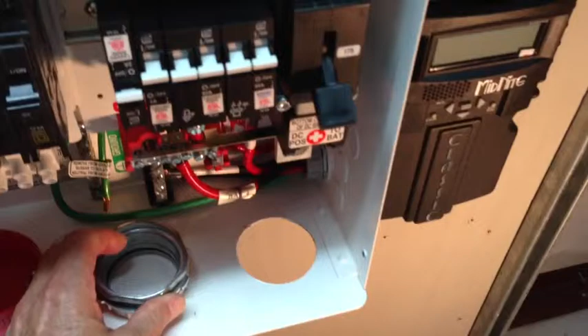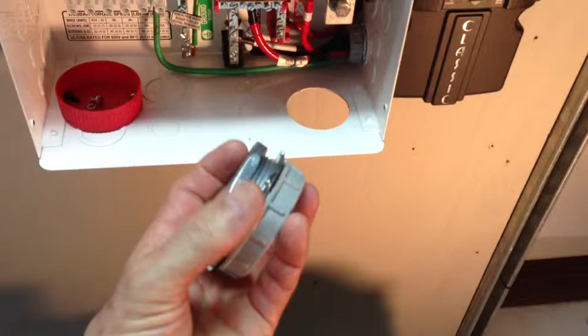This is where the main battery leads are going to come through into the box, and I needed something to keep the wires from chafing. I was looking for a 2-inch diameter nipple about 1 inch long, and found out those aren't made, but these chase nipples are. It's got a nut on one side, smooth on the inside, and you can put one of these plastic rings on it to keep the wires from chafing, and mount that into a very thin piece of metal. That's going to work out real well, so I'm happy with that.